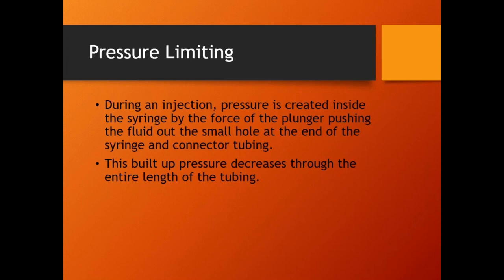Now, before I get specifically to pressure limit, and again, I apologize, I know everybody probably can't see this, this is the display where the operator is going to enter the parameters for the injection. That is connected to the patient. That's a CT injector. When the operator wants to do an injection on the patient, there are three things the operator has to select. There's a bunch of things they can select, but three have to be selected; everything else can be zero, but these have to have something: flow rate, volume, and pressure.